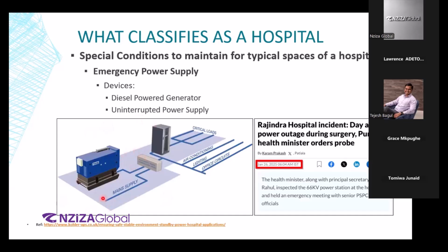This is a short schematic, not anything in detail, but we will speak about it in detail as well. Of course, you will have the DG set. You will also have the main supply supplying the power from the switchboard, distribution panel, whatever it is. You will have the automatic transfer switch over here, and then we will also have the UPS. The UPS is going to serve the critical loads. Lighting, office circuits, air conditioning for non-critical areas can go on the DG set, but critical loads need to go via UPS. So, special consideration for hospitals.